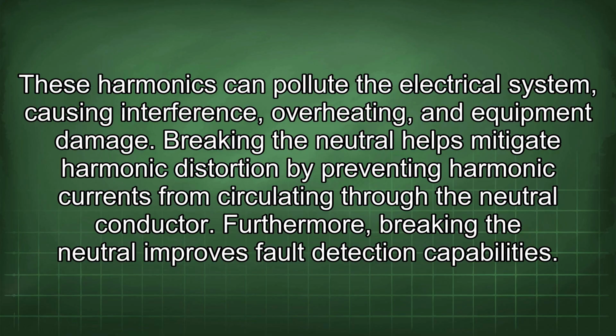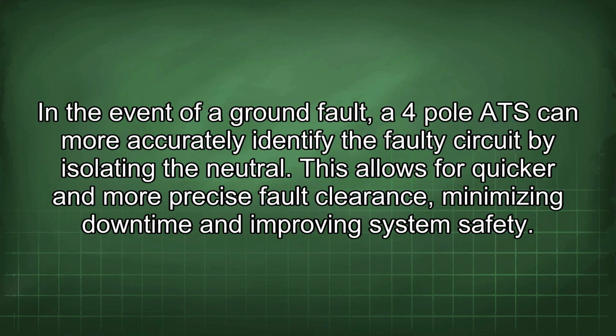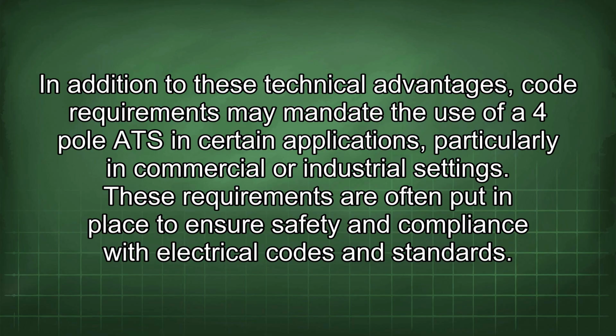Furthermore, breaking the neutral improves fault detection capabilities. In the event of a ground fault, a 4-pole ATS can more accurately identify the faulty circuit by isolating the neutral. This allows for quicker and more precise fault clearance, minimizing downtime and improving system safety. In addition to these technical advantages, code requirements may mandate the use of a 4-pole ATS in certain applications, particularly in commercial or industrial settings. These requirements are often put in place to ensure safety and compliance with electrical codes and standards.